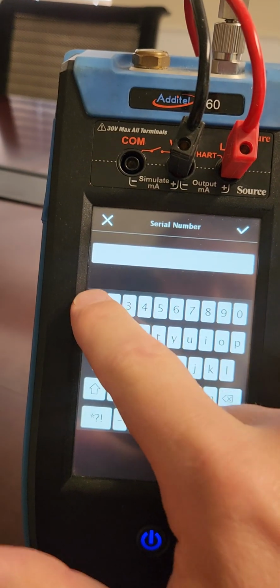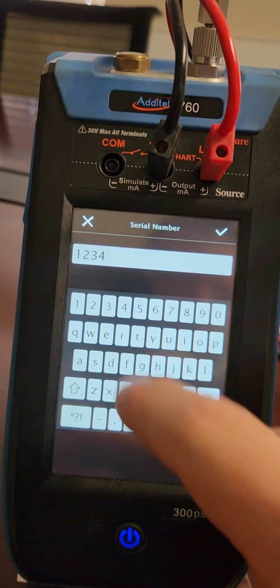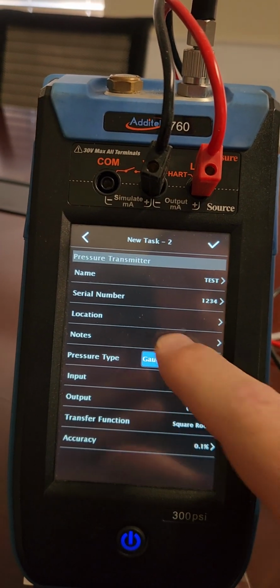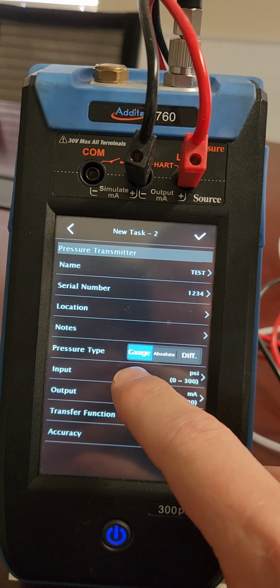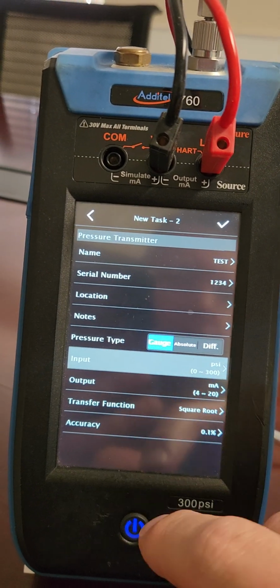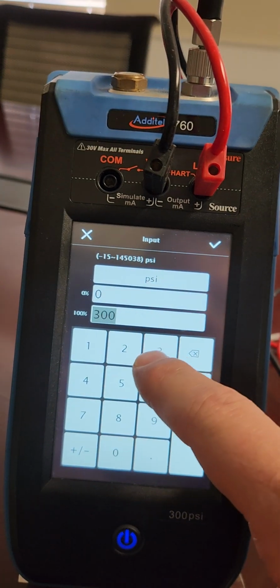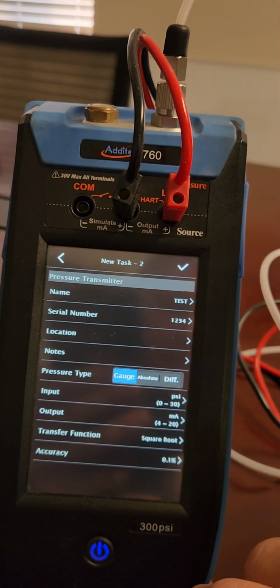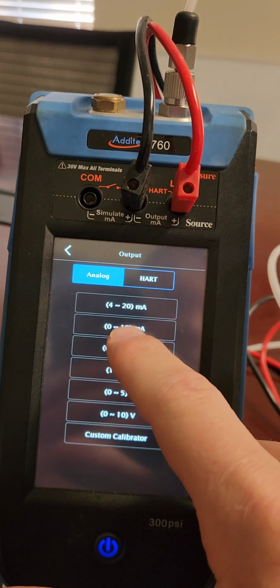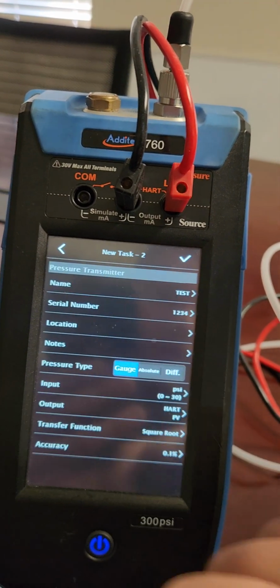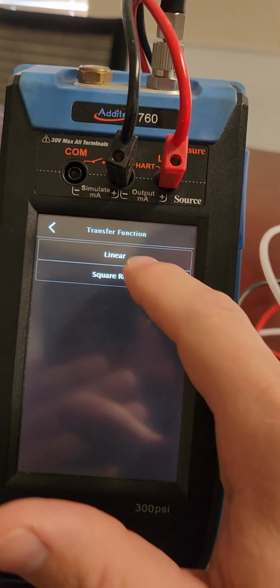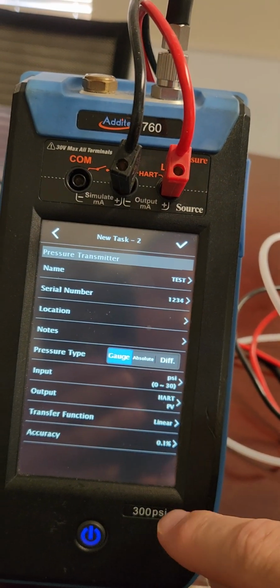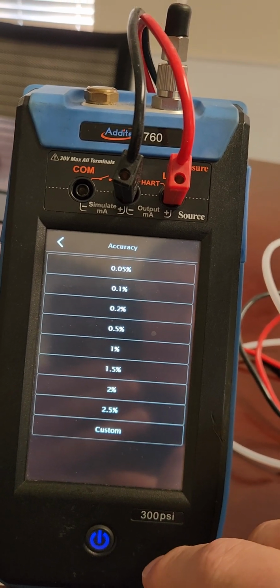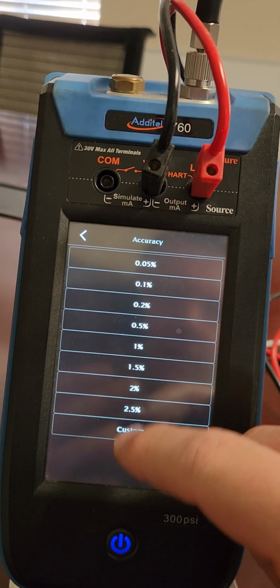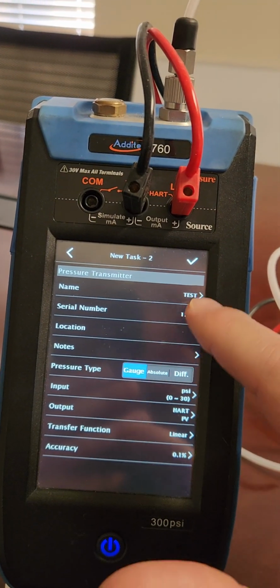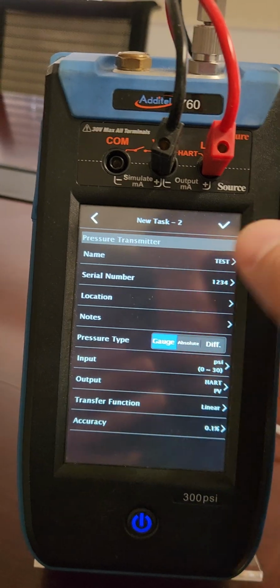Enter in a serial number for the device. Let's do 1, 2, 3, 4. Location, you can put that in, any notes if you want. We're doing gauge pressure. Pressure range, so where you'll select. So right now it's 0 to 300, this is a 0 to 30 transmitter, so we'll select that. Output, right now it's set to 4 to 20, so we're going to go Hart and we'll do pressure. Transfer function, whether it's square root or linear, so this is the linear one. And then you can designate the accuracy of the device, so whatever that is, I'm going to set it at 0.1%.